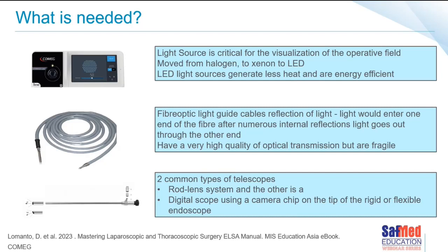The light source itself, of course, is critical to the visualization of the operative field. If there's no light, we can't see, and in these cavities, it's pretty dark. And if we're doing stuff in the cavity like cauterizing or there's blood or anything of the sort, it becomes harder and harder to see. So we've moved over the years from halogen to more xenon-based light sources, and of course nowadays we have LED technologies. LED light sources generate less heat, and they generally are more energy efficient.